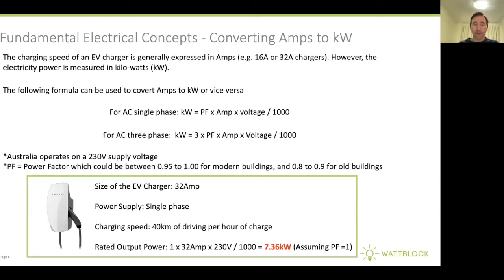PF stands for power factor. In a modern building, that's usually between 0.95 and 1.00. Older buildings might be 0.8 or 0.9, and some really bad buildings might have a power factor of 0.6 — which you should be doing something about. The AC single phase formula: kilowatts equals power factor times amps times voltage divided by 1000. For AC three phase: kilowatts equals 3 times power factor times amps times voltage divided by 1000. The worked example shows a rated power output of 7.36 kilowatts, assuming the building is operating at a power factor of one.